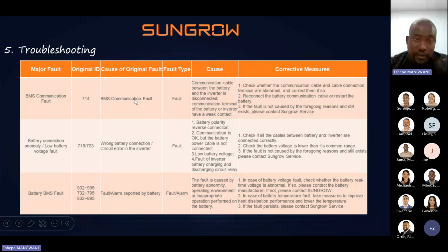ID, it will be BMS communication fault. A fault type, it's a fault, yes. What is the cause? Communication cable between the battery and the inverter is disconnected or not connected correctly. This is where we connect our CAN high, CAN low, stripe orange and white, and solid orange communication.